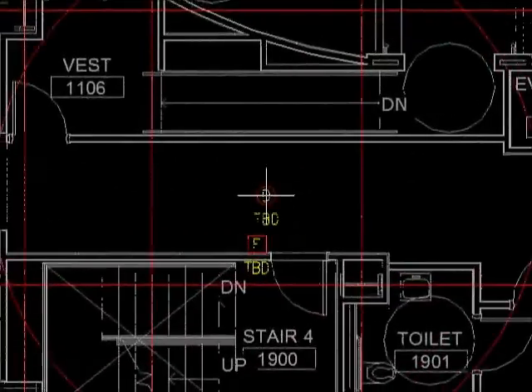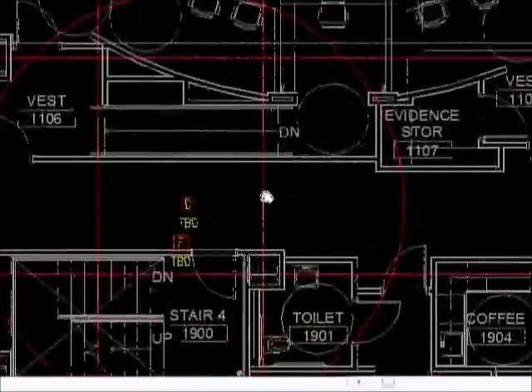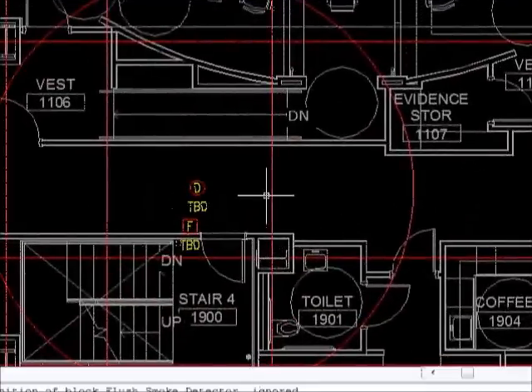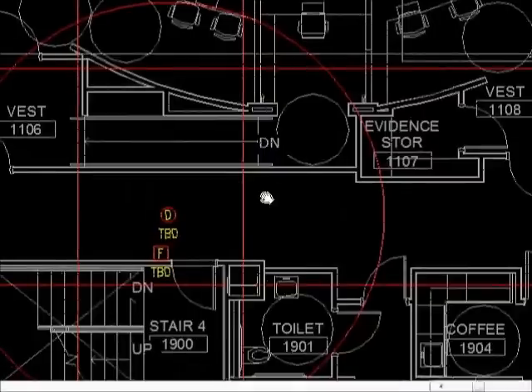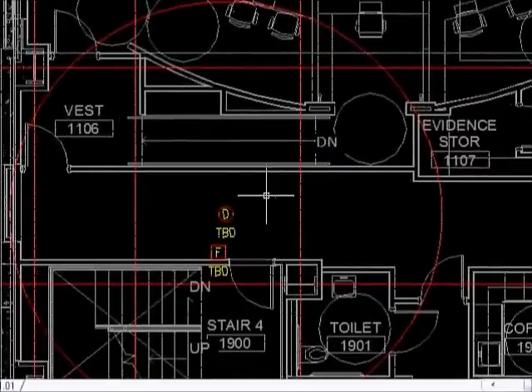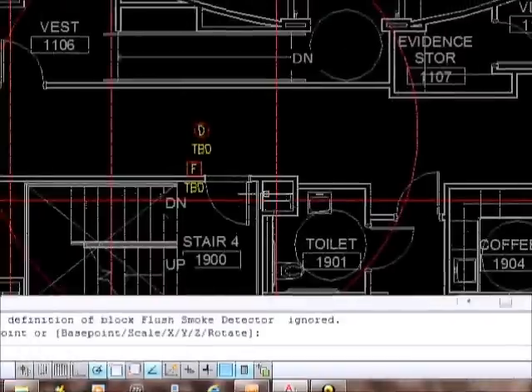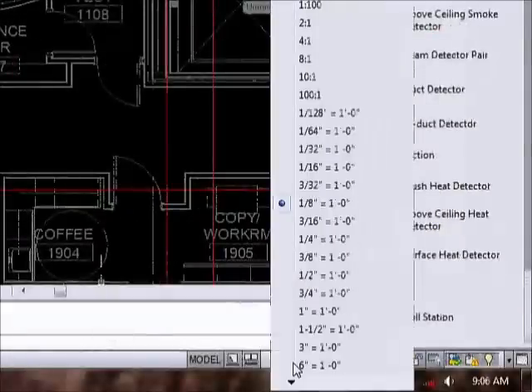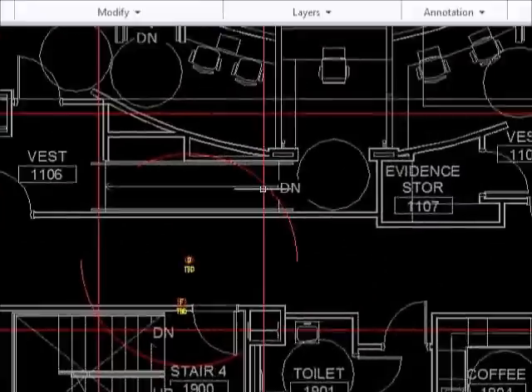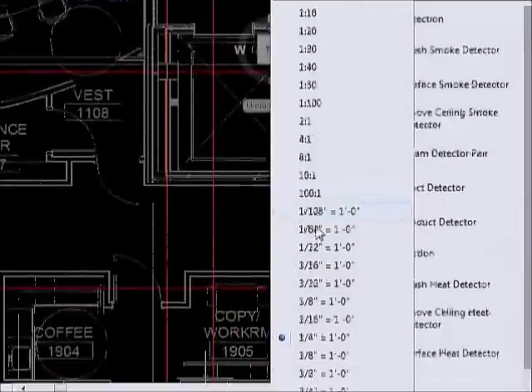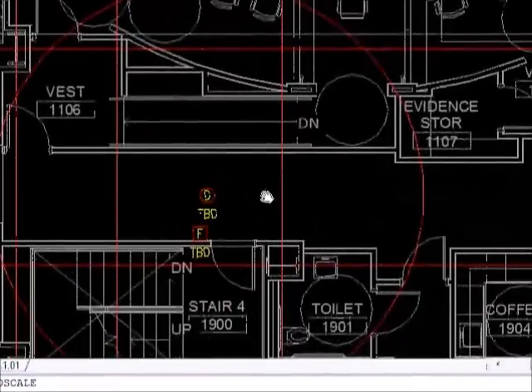Please note these templates only apply at 1/8 inch equals 1 foot scaling. So if you are needing to do a drawing at a scale other than 8th inch, go ahead and set your annotation scaling to 1/8 inch. And then once you're done with your drawing, you can reset your scale to whatever scale you want. But the templates will not be accurate at other scales. They're only accurate at 8th inch, so always use 8th inch scale for placement.